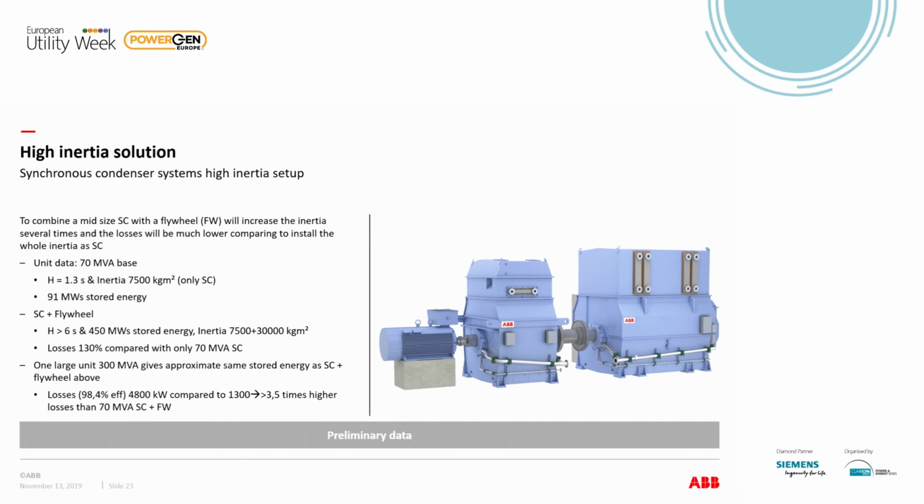And that is also the way why we would like to use this type of smaller units, of smaller synchronous condensers, with a lower MVAR rating, with a higher inertia in those areas where we need the support. Because we don't need these big machines in those remote areas. Because normally a condenser is working with very, very low MVAR values based on the fact that you don't need the MVAR so much. So that means that the losses would be too high if you install a big unit. That's the reason why we say that smaller units or multiple units, it's better than big animals.